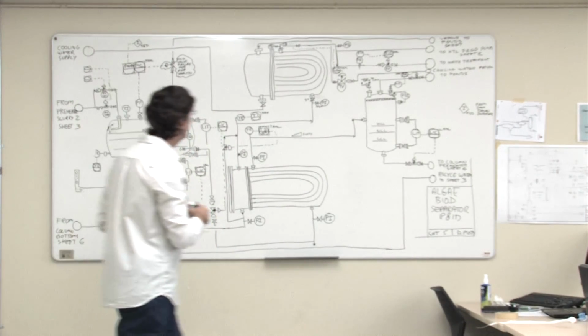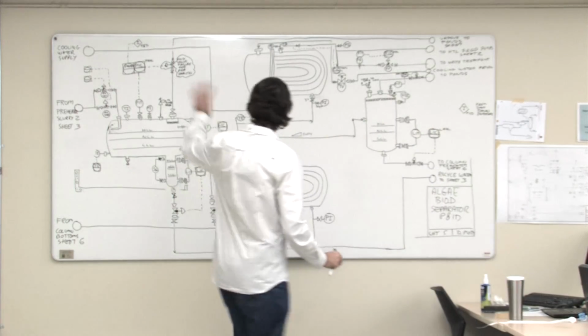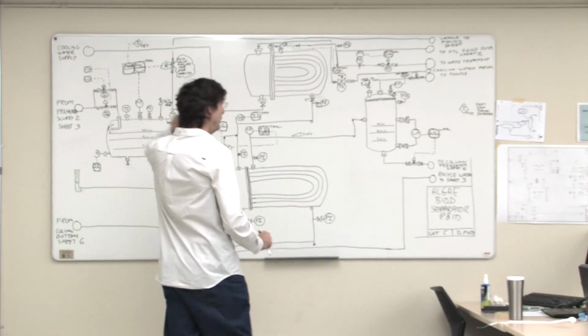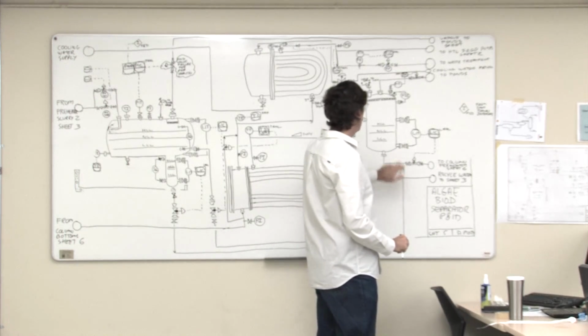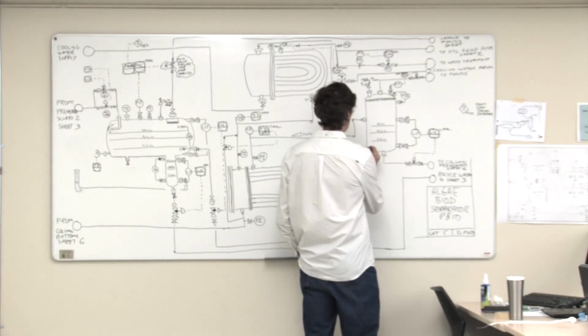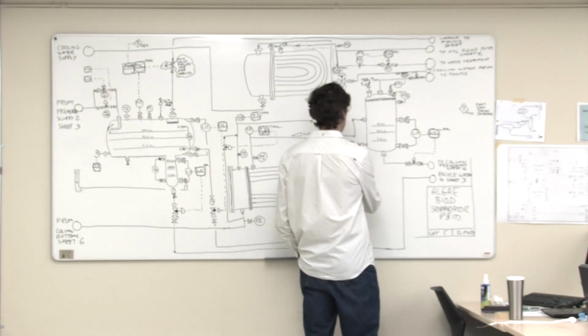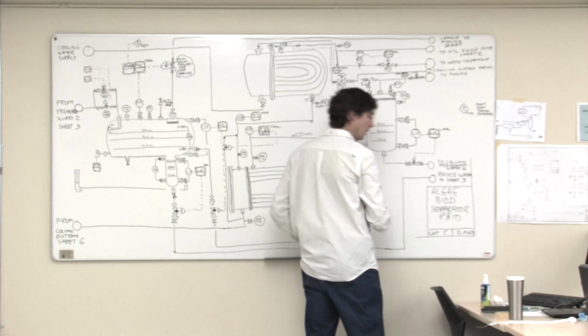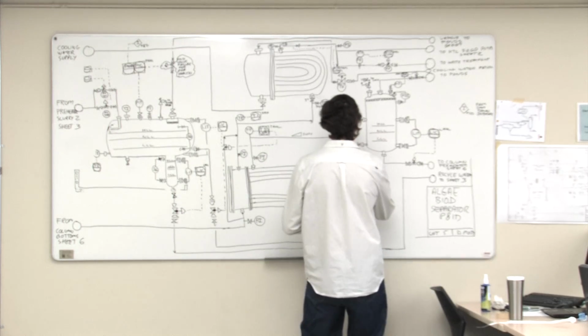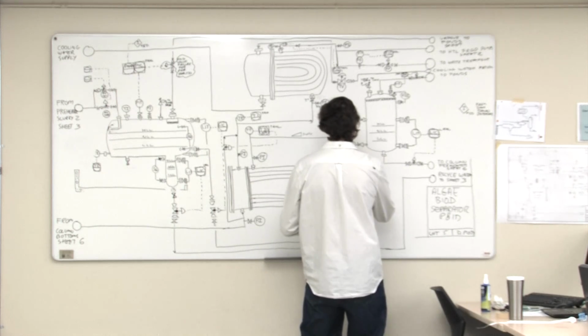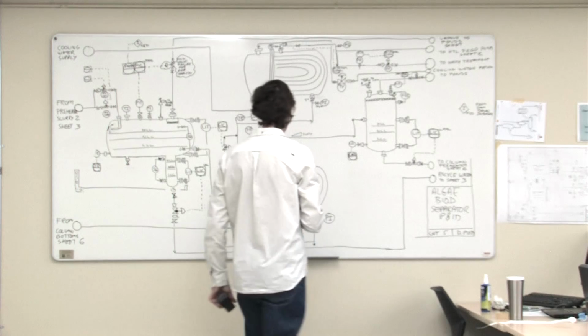I think I'm actually done except for interlocks, you guys. So we did put one interlock on here. If we're really worried about this level transmitter maybe not working, then we might want to put a level switch low on this. If we did, then we tie it into a level alarm low, like that. And then heaven knows what we would actually shut.